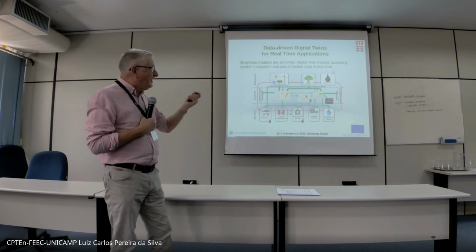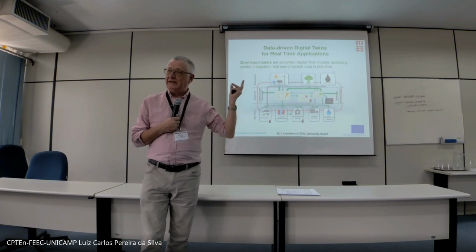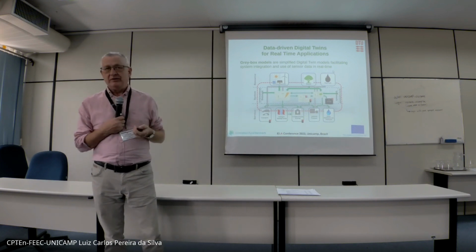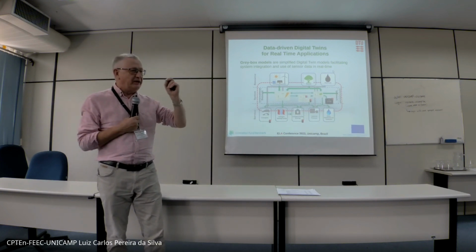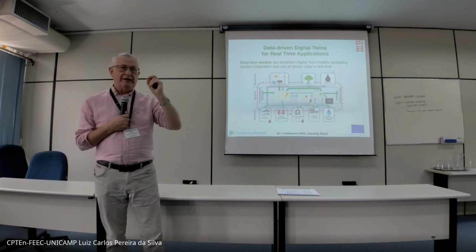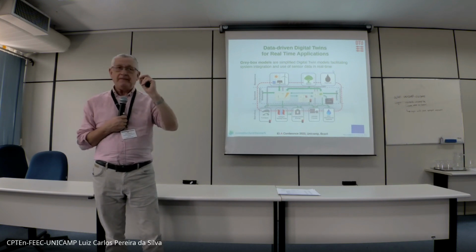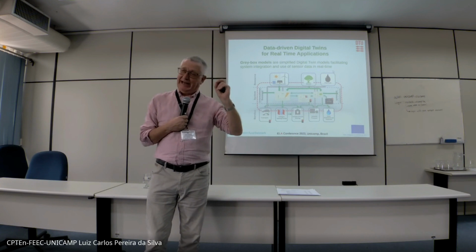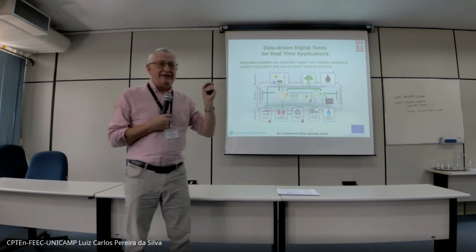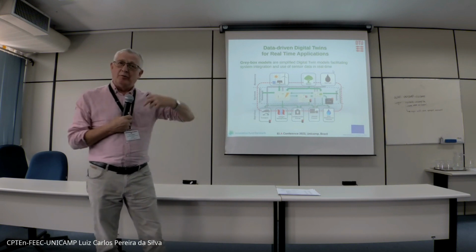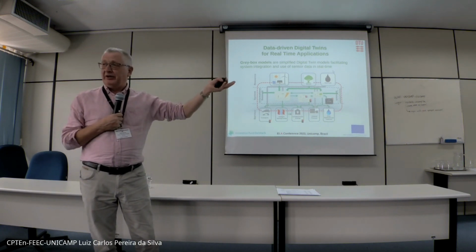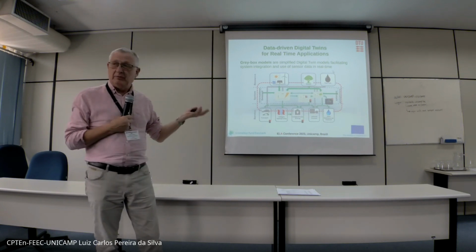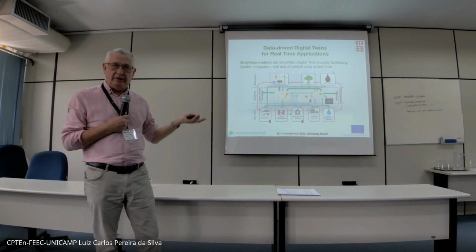Another thing which is important is that we need to be able to do this in real time. And the first model we got for wastewater, we're doing a lot on smart wastewater handling, some 15 years ago was a model with 43 coupled nonlinear differential equations. And it took us 1.5 hours to calculate what will happen in 5 minutes. Maybe we could have been smarter, I guess, but it was not really useful. So we threw away these deterministic differential equations and replaced them with gray box models and stochastic differential equations. I think today we have 6 coupled nonlinear stochastic differential equations.